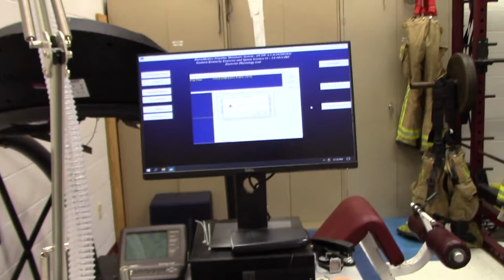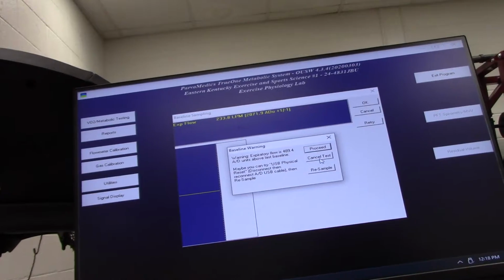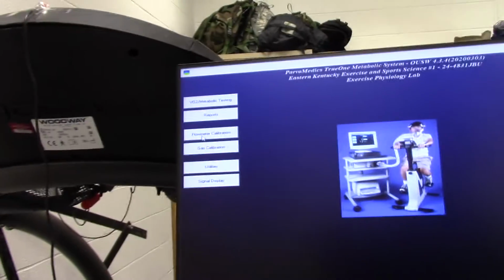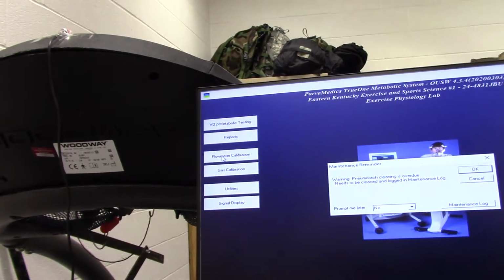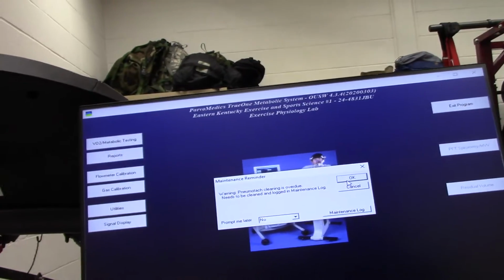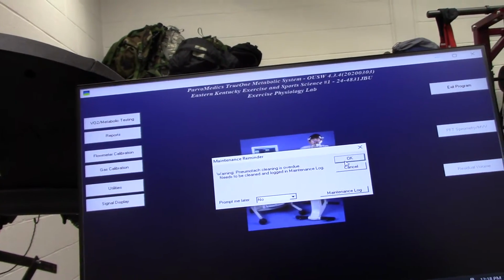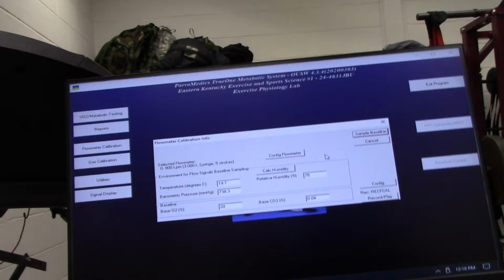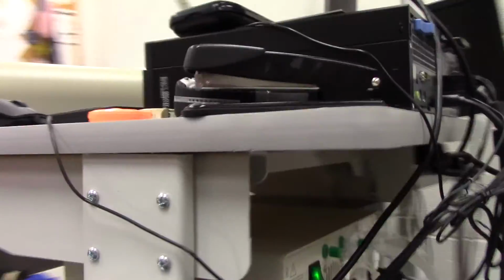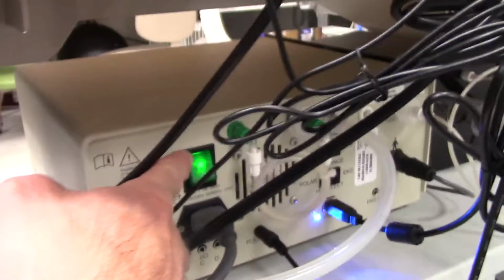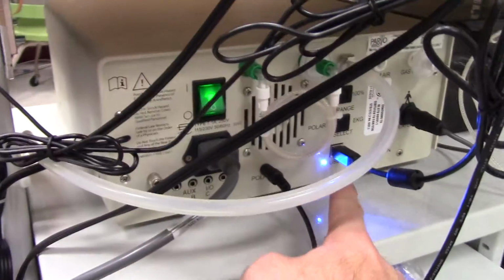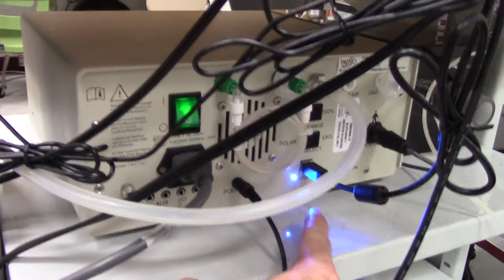So, when we're calibrating the metabolic cart, the first thing we want to go to is what's known as flow meter calibration. We're okay with our cleaning, we've done that recently, but ask questions if you need to. Now, we need to make sure that we've turned on the VO2 measuring ahead of time. So this should be switched in the on position. We see our green or blue light, where we're getting information through the USB into the computer.